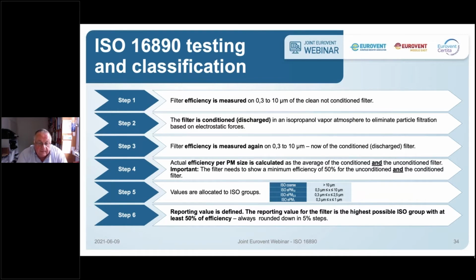The next step, step 2, is that the filter will be conditioned, meaning it will be discharged. This is necessary because there are filter media in the market with quite good filtration efficiency when new and unused, due to electrostatic charge, but they lose that charge over time, and the efficiency ends up at a much lower level. To get a reasonable average of the efficiency over lifetime, for both the new and used filter, we simulate by discharging what happens over the lifetime of the filter.